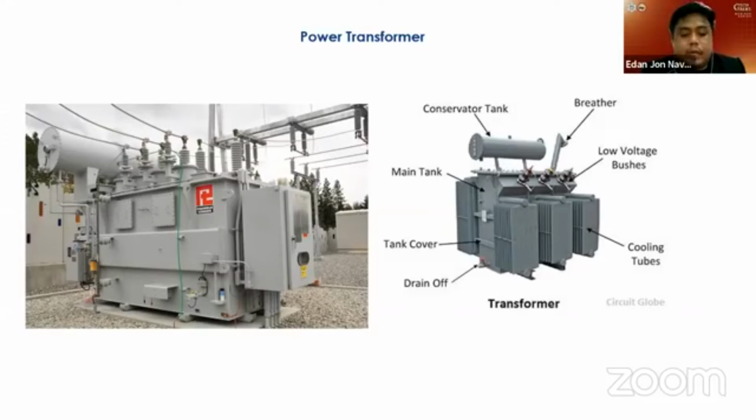Due to very high power generation, the construction of power transformer is also critical. The construction includes solid insulation and a well-balanced cooling system. The most common power transformers are filled with oils. The main principle of power transformer is to convert the low voltage, high current to a high voltage, low current. This is required to minimize power loss in the power distribution system. Another important parameter for the power transformer is the phase availability. Typically, power transformers work in three phases, but in some cases, single phase small power transformers are also used.